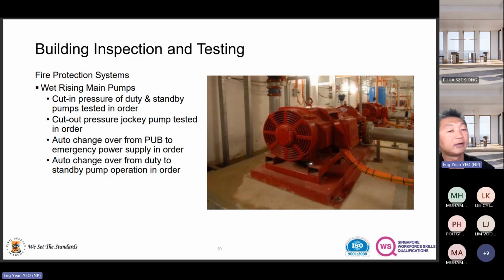If not, you would consistently have the fire alarm going off in the building. That's why the jockey pump is the one that pushes back to 180. But if the jockey pump is unable to push the pressure back to 180 and it keeps on dropping, even at a very slow pace, when it hits, let's say, 150, the electric pump is supposed to kick in. So that testing, in fact, is supposed to happen during your monthly inspection, or the monthly servicing or maintenance of your sprinkler pump or your wet riser pump.